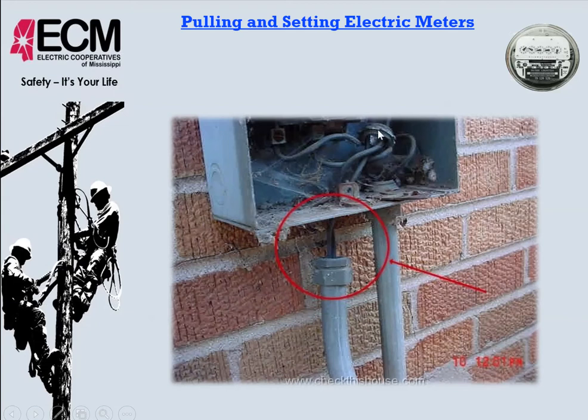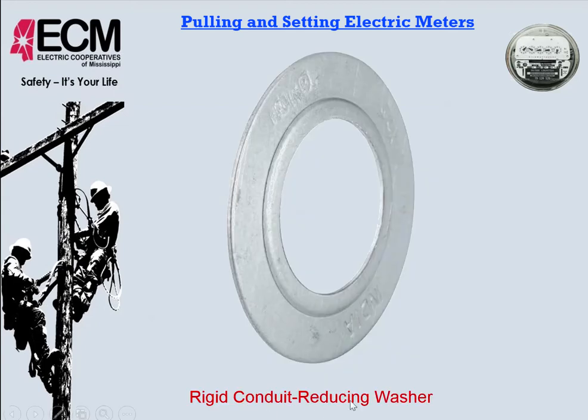Actually, you see the lock ring right there that would come down and fit on top of this. So you need to make sure that that's sealed up and in good shape as well. They make a rigid conduit reducing washer. So if you inadvertently end up knocking out the wrong size that's too big for the metal adapter that you have, that fits on the size pipe that you have, you can get one of these things that will cover the gap, have the ring on the inside that your lock ring can hit on, and making sure that we're having that secured to the pipe.